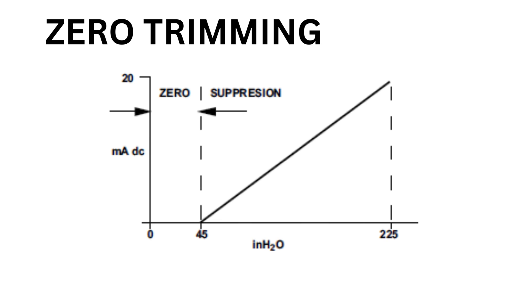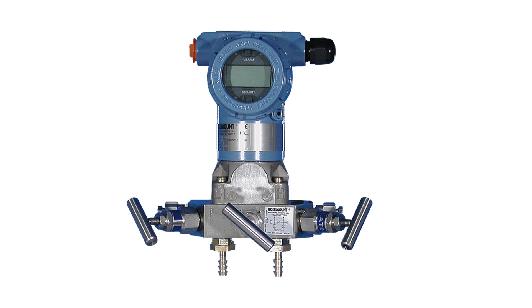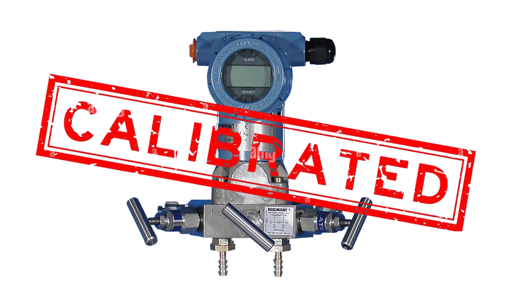Now check the 100% flow point by applying the 100% DP pressure to the input of the transmitter. If the reading does not indicate 100% flow, perform a span trim using the HART calibrator. When the zero trim and span trim is completed, the transmitter is calibrated.